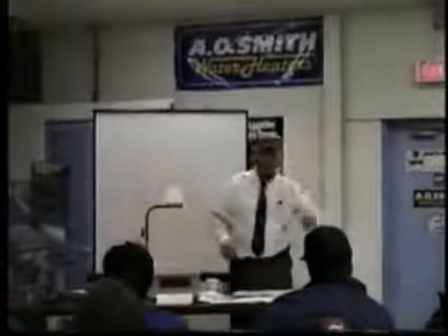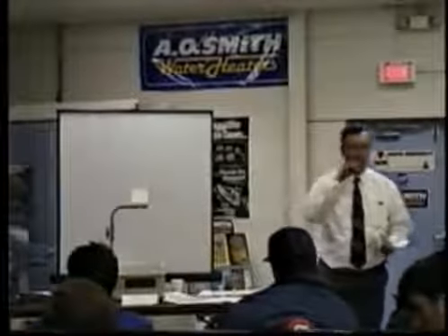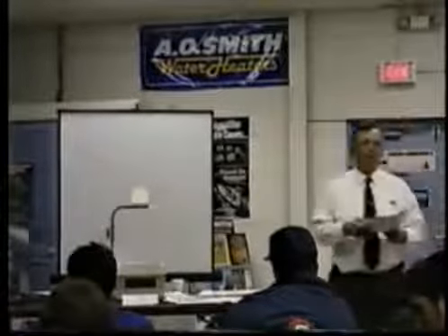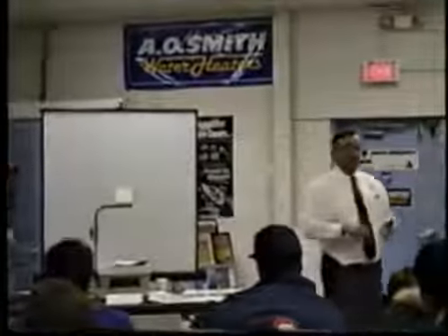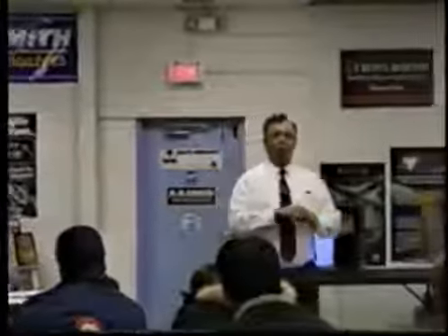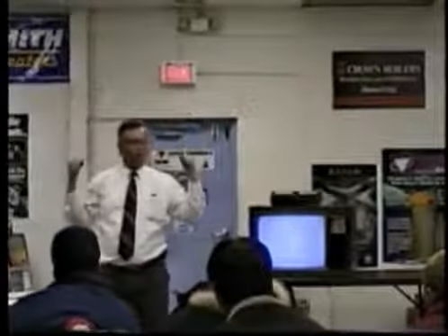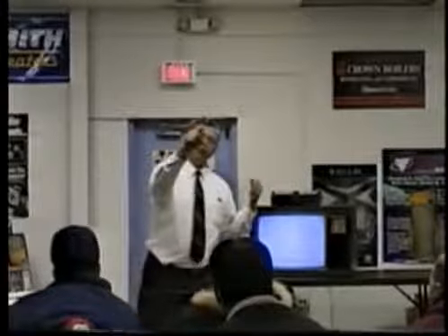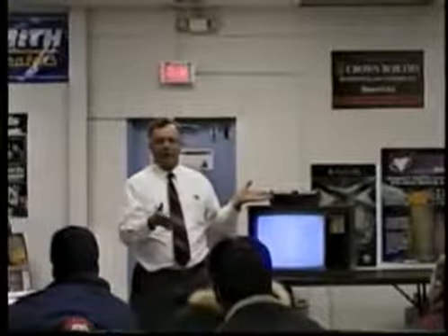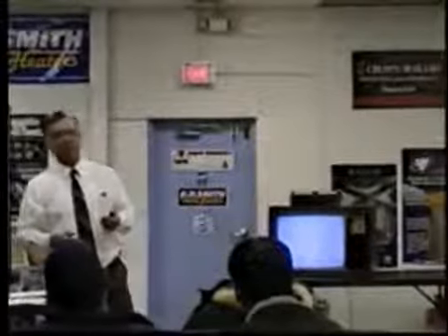Okay, yes, question? On the opposite end, like you're saying, with too small of an air conditioner, it dehumidifies well. Yes. And if it's too big, it's my understanding that it cools it, but it doesn't dehumidify. Yes, excellent question. Thank you for asking that, because the other side of the coin is what could very easily happen. An oversized air conditioner on a 100-degree day, again, it will cool so rapidly. It's an excellent air conditioner, excellent cooler, but it cools so quickly it shuts off. It's supposed to be running 100% of the time on a 100-degree day. Yeah. But if it shuts off, because maybe it's big enough to cool the house if it was 150 outside.